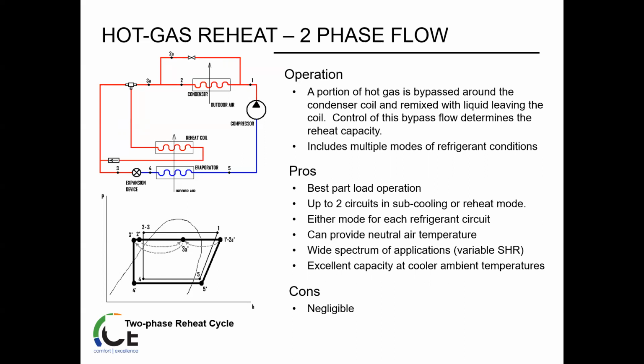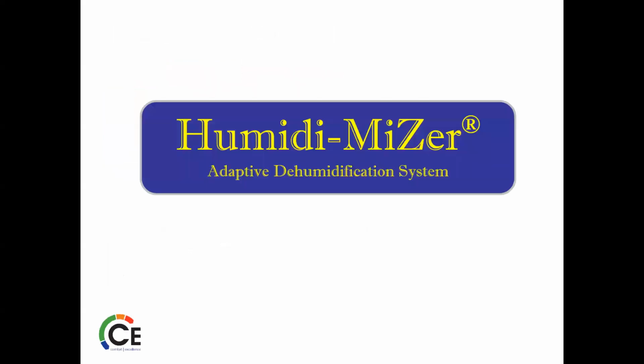A lot of pros, no cons really here. The three-way valve introduces or removes the coil. So now we're starting to meter that a little bit, trying to keep that overheating from happening or getting past the neutral temperature. The advantage to this system design is the multiple options available for controlling the refrigerant flow. So now we're in two-phase, controlling that flow a little bit to maximize what we're trying to do here, without reheating the air or overdoing whatever.